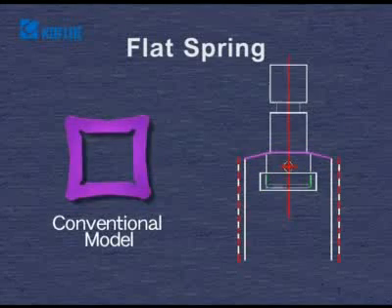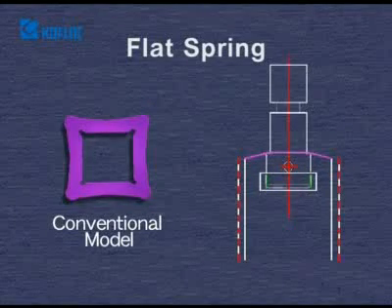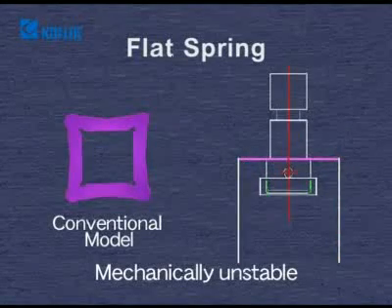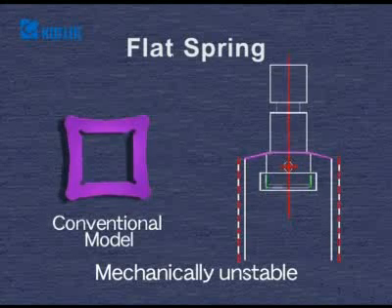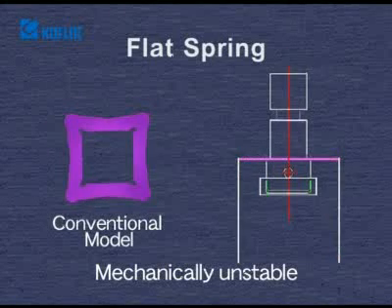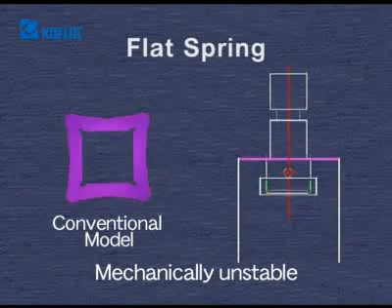When a voltage is applied, the plunger and magnetic bar attract each other. When the magnetic flux distribution is non-uniform at that time, the movement of the plunger will be eccentric, causing friction in the inner wall of the plunger housing.